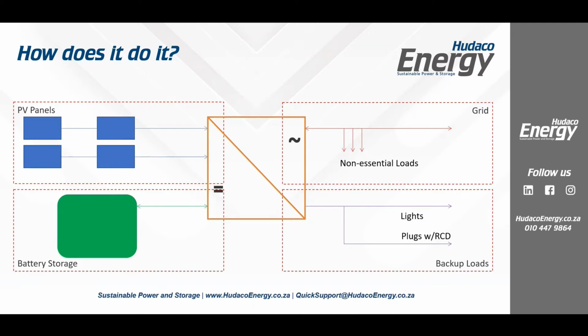How do I do that and still not export power? Well, we have a current transformer, a CT, which is supplied in the box for you, and we install that right here at the grid connection. So we detect voltage at the inverter, and we detect current right at the grid. So long as this current is not exporting, I will continue to provide power here from PV, or even, if I set it that way, from my batteries. So let's say it's 7 o'clock at night. I could run my pool pump, if I wanted to, off my battery power.